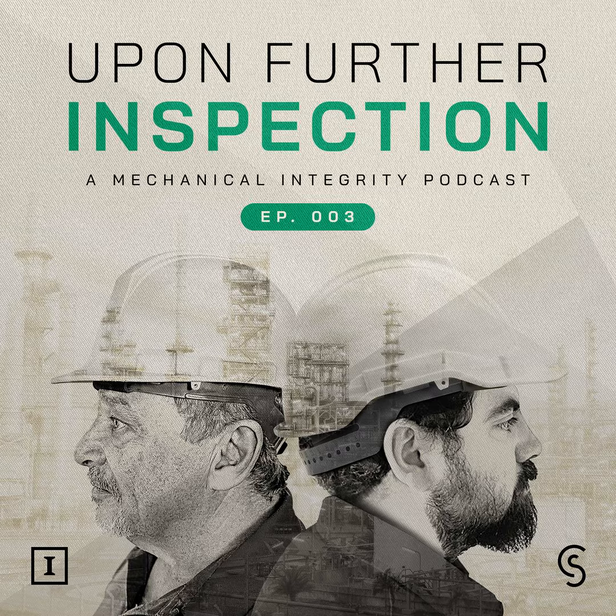And back in the day, we used to have manways on PSA vessels. 15 years ago, 20 years ago, they quit putting manways on them to reduce the stress risers. And they just put an oversized top head center nozzle on them so that when you went inside, you could go through there instead of having a separate manway on the sidewall. Yeah, because the fatigue would be way too much. Yeah, it's like eliminate stress risers as much as possible.